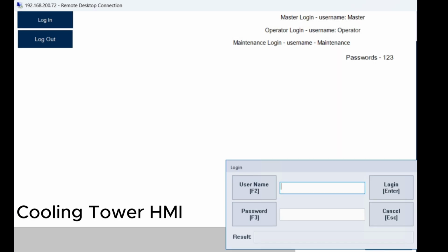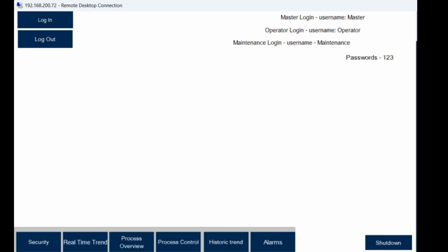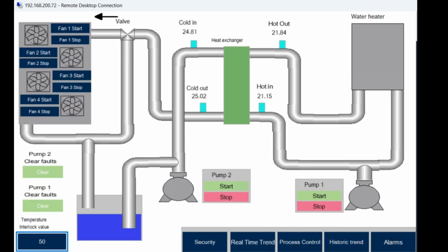Alright, for our HMI, we got our security page here. Go ahead and log in. And I'll go ahead and start at our process overview page. So we have a manual start and stop for each of our fans only when we're in manual mode. And here we have our clear fault buttons for our pumps. And then we have an interlock temperature value right here that is adjustable. We can set that. And our start and stop for both of our pumps and our water heater that shows if it's on or off. It's off right now. And we have each of our hot out, hot in, cold out temperatures.